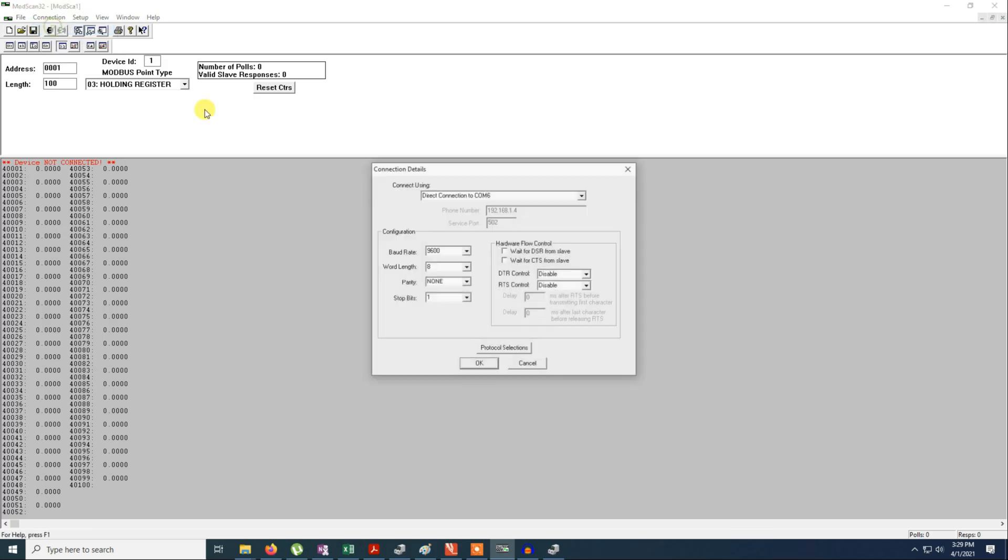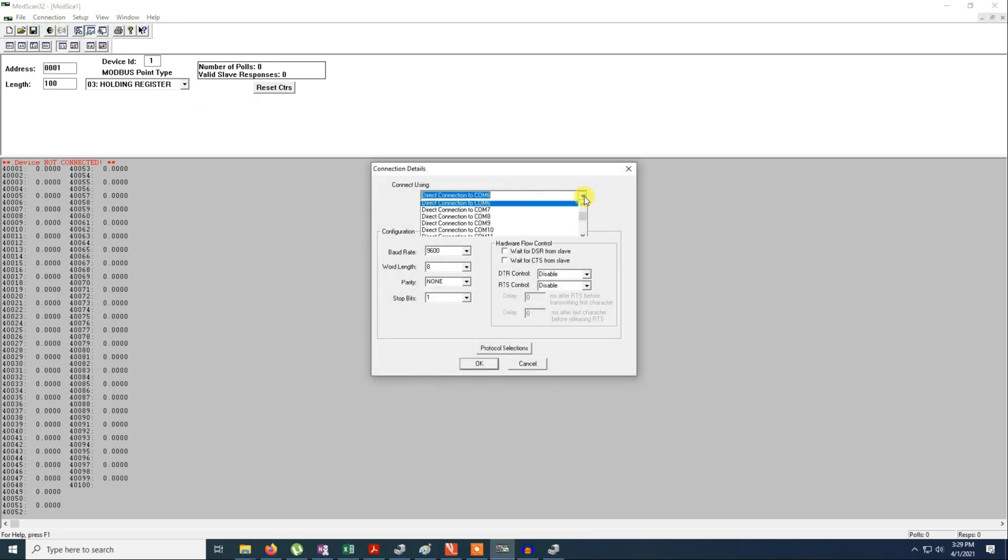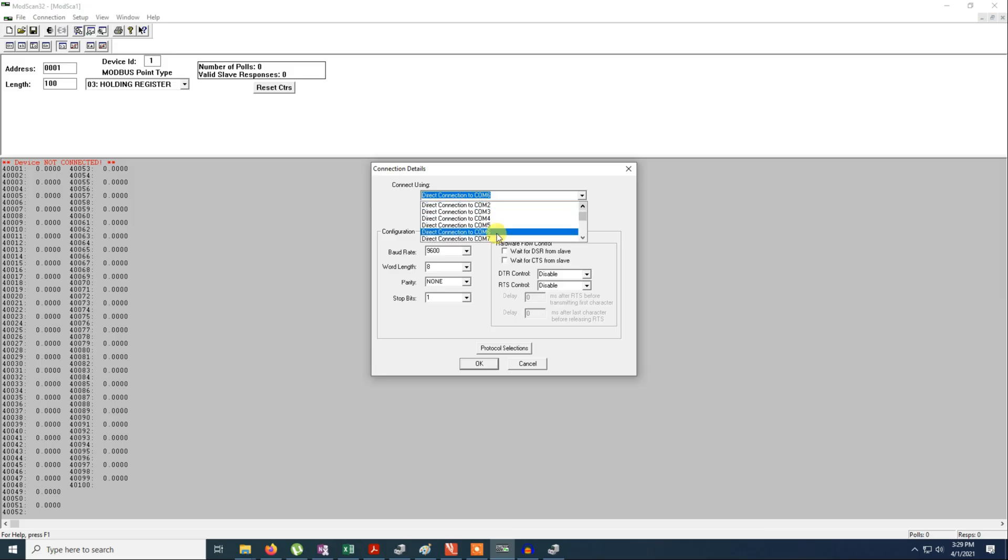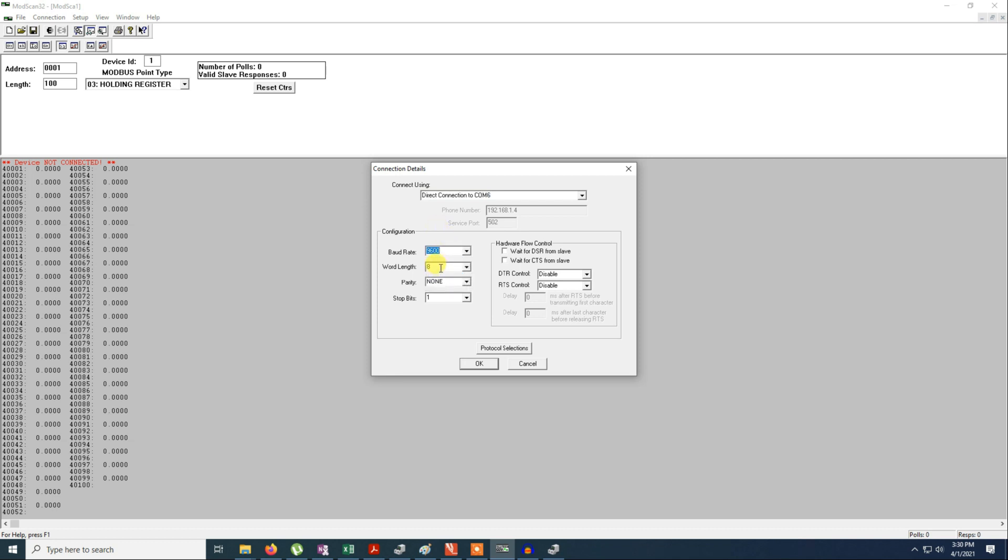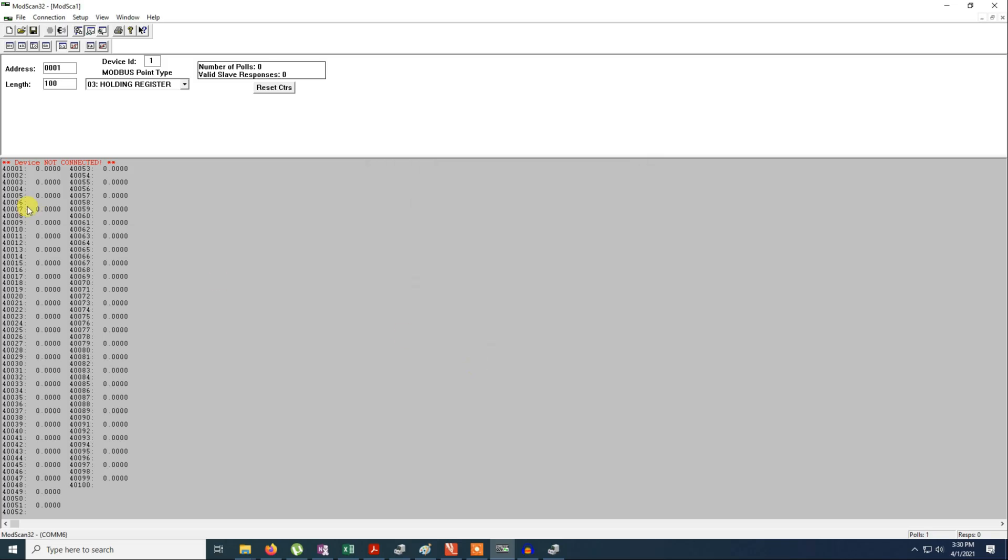And it's connected on the COM port 6. You come here on the MODBUS. It's MODBUS data scanner. So now we make a connection to the device. We click connect. You go to COM 6. You set the baud rate which I have already set on the device, 9600, the word length, the parity and the stop bits. These parameters should be set also on the device. You click OK. But you will see there is no connection. Why? Because on this device I have given the address number 2. So we just put the address number 2.